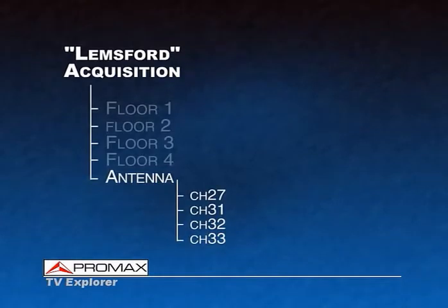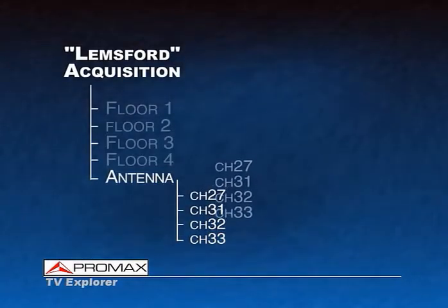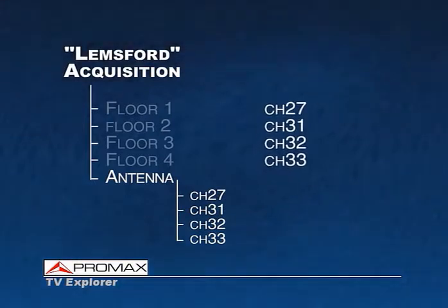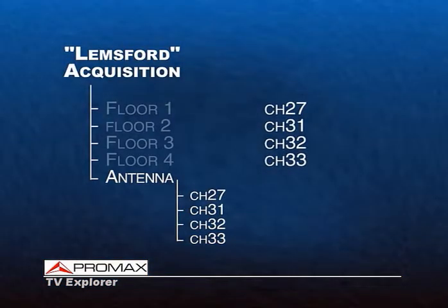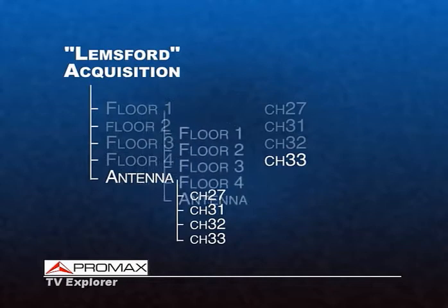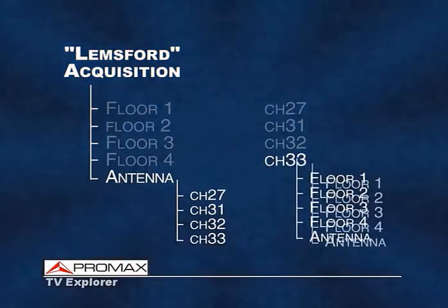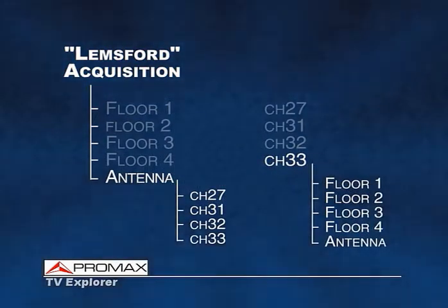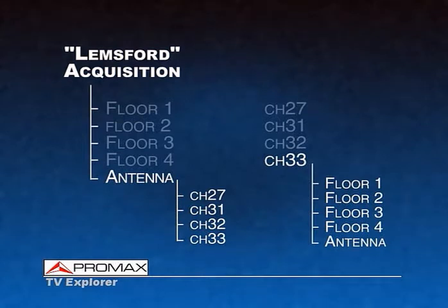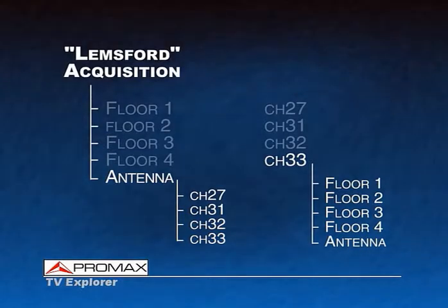It is also possible to display the recorded data in a different way: by selecting one specific channel — channel 33, for instance — and viewing the data corresponding to that channel at the various measurement points. This is quite helpful to see how the signal varies as it travels through the distribution network. If there is a problem somewhere in the installation, it can be immediately detected by noting the name of the measurement point.